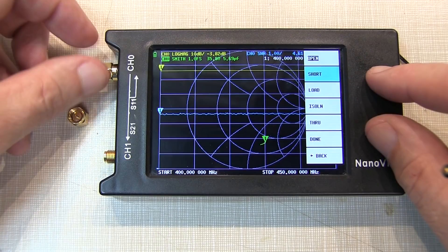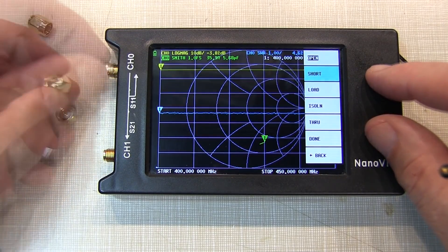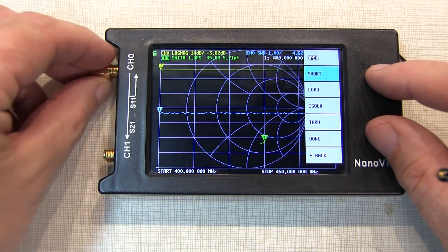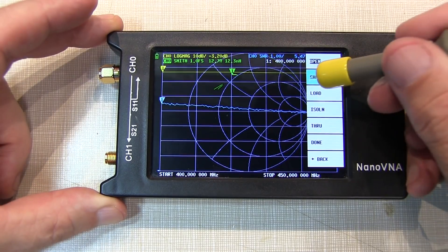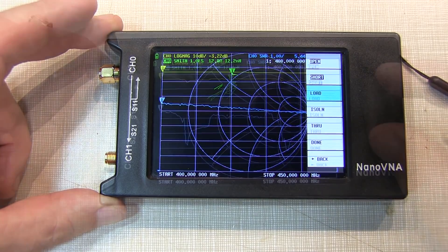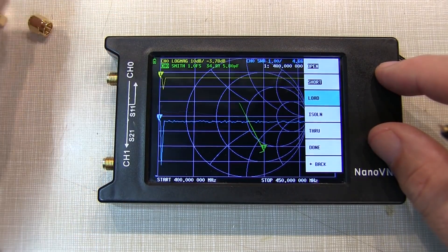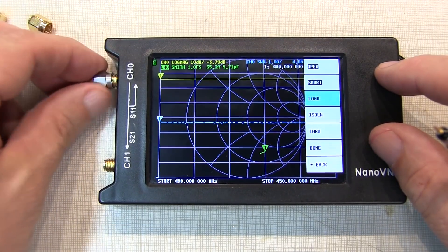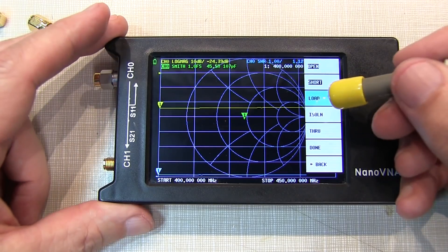So we remove the open, and attach the short, and then touch short. Now once the short is done, we're ready to do the load. So we remove the short, and attach our 50 ohm match for the 50 ohm load, and touch load.